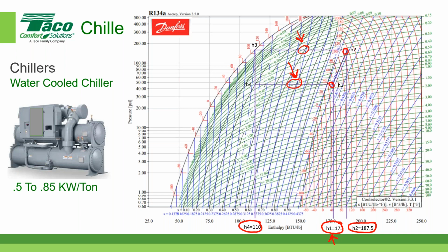So if I can increase my supply water temperature, let me erase these lines because it gets a little confusing here. If I move this line up, you can see, let's say I draw a line over here, then now I have less work to do out here on my compressor, delta H. And if I can lower this line down here, you can see that that becomes even smaller. So the key to making a chiller plant efficient is to try to get the supply water temperature as high as possible and the condenser water temperature as low as possible.